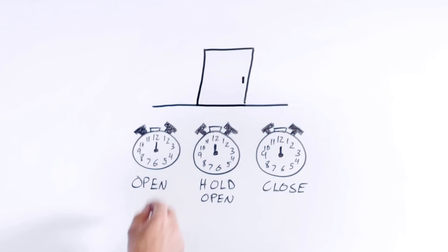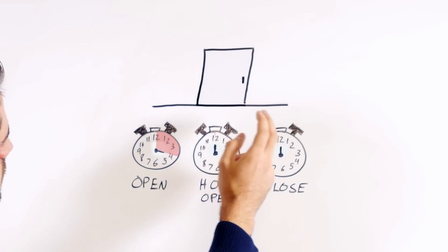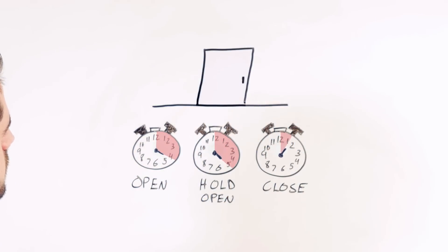And it must take at least four and a half seconds to close a typical door. These opening and closing time requirements increase as the weight and size of the door increases and are defined in A156.19.